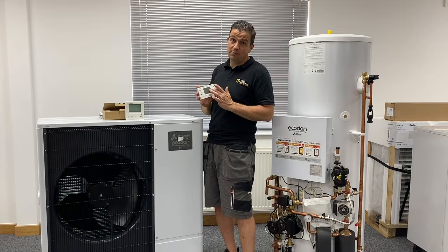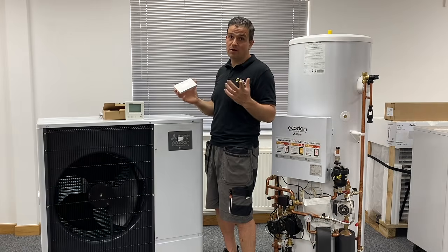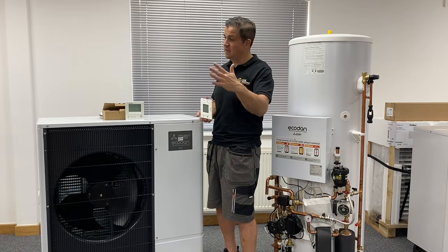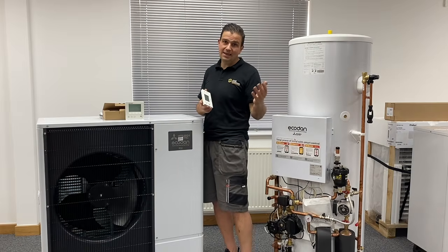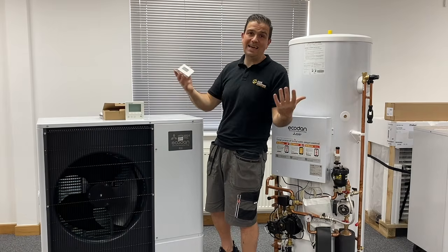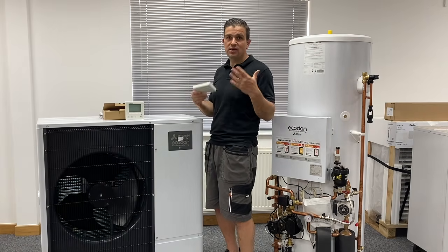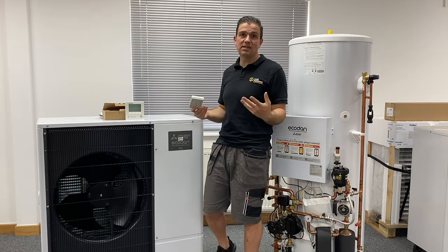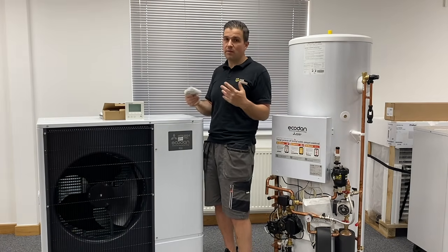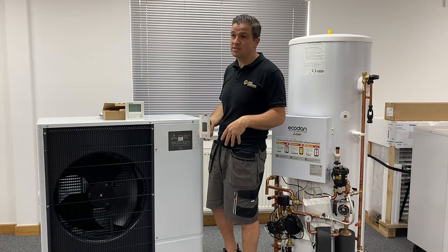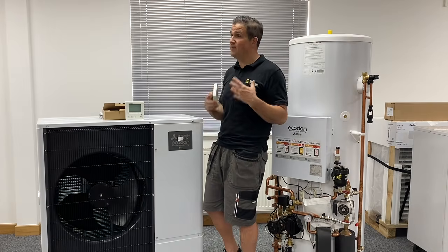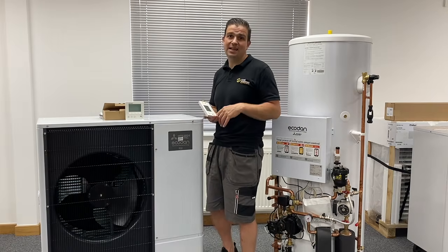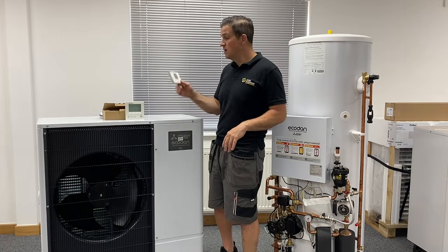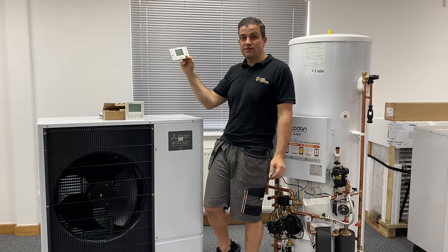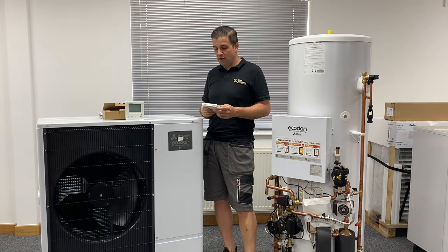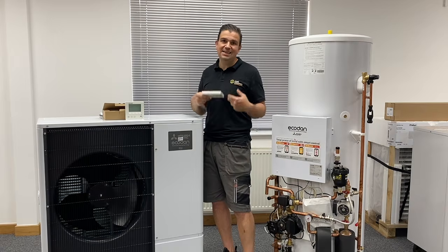It will come up with a display which has temperature on it, and it will be an up and down to select your temperature, and it will take a few seconds to signal to the heat pump, okay, I need heating coming on. It will be placed, I don't know, it could be on a landing, more than likely a landing rather than a bedroom, because whatever room the thermostat sits in is what determines the temperature it will meet, and so it will give a better balance. And TRVs obviously on radiators sized suitably for the rooms. If it's existing radiators, a power flush, making sure that system's clean and working as efficiently as it should do. You can actually get multiple zones of these receivers as well, so you can control more than one area, but we would look at the design and the property and just see what would work best.